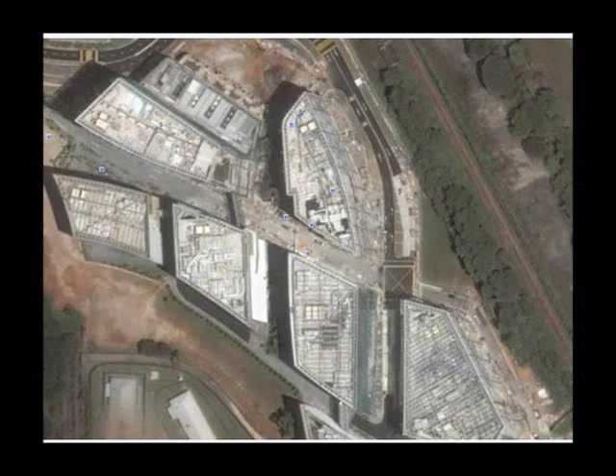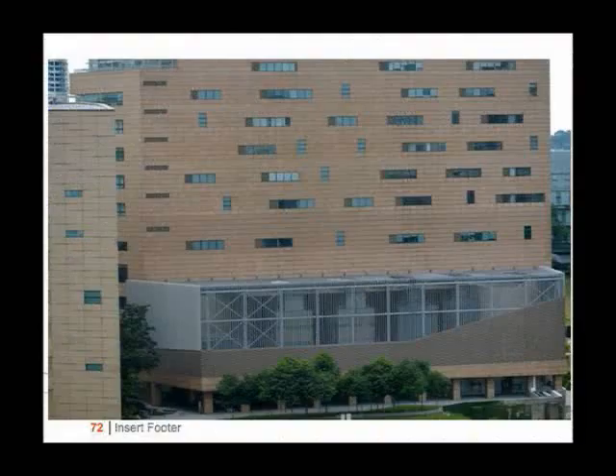Singapore, new district cooling plant. Cooling towers, Google Earth. Take my Nikon D700 and you go to the building across and you see, my goodness, the towers are squeezed together. How will the air flow? So I made a little inquiry to one of our sales guys and he said, how did you know? They just ordered the new chillers with 32 degrees C inlet water because the old chillers were selected for 30 and they cannot handle it because the towers are not working. So now the new chillers are much worse efficiency. There are so many train wrecks in slow motion.